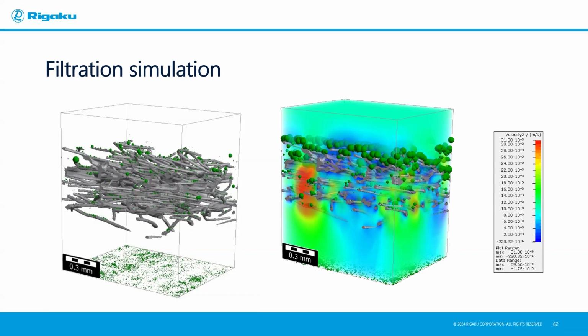And in this case, we see on the right, this red color is associated with the velocity of the particles. So some are moving very fast, some are moving slower. And in those areas where binder is, you might intuitively expect that flow would be slower than it would be in other areas. So you can characterize this in a number of different ways. But what you probably notice is that from this experiment, we don't really see that the simulation represents the total dust holding capacity of the filter.